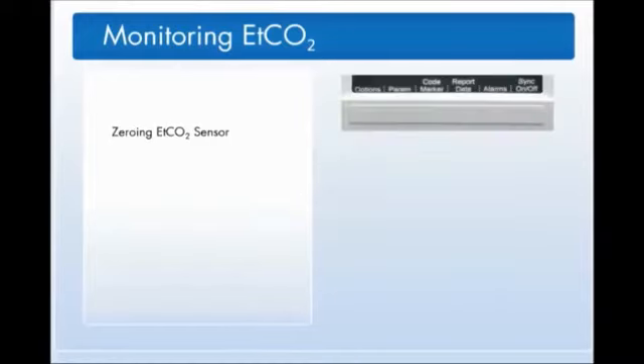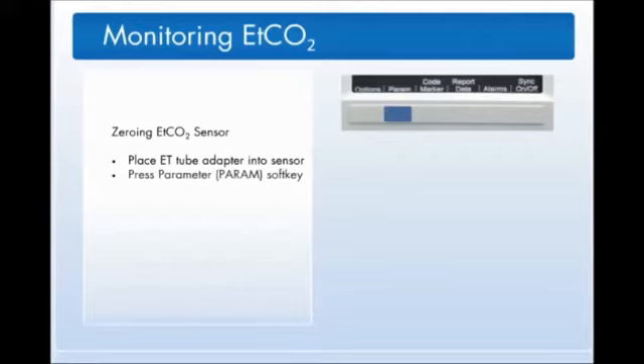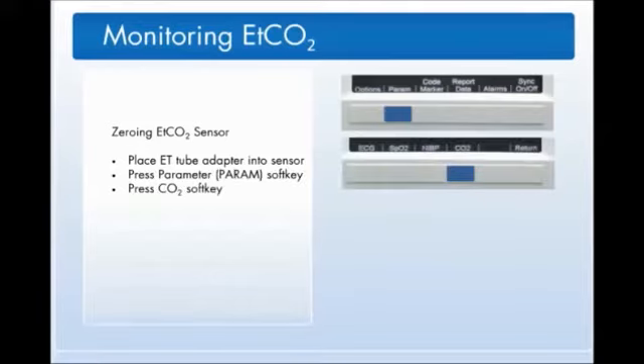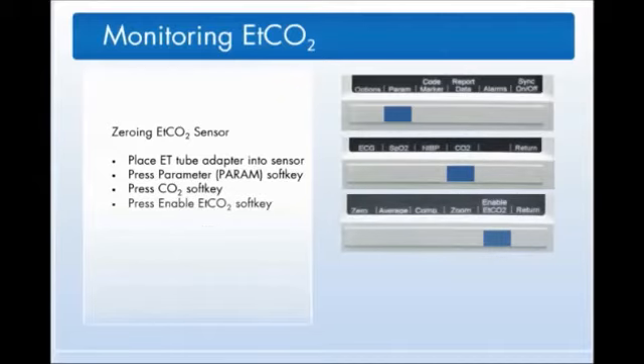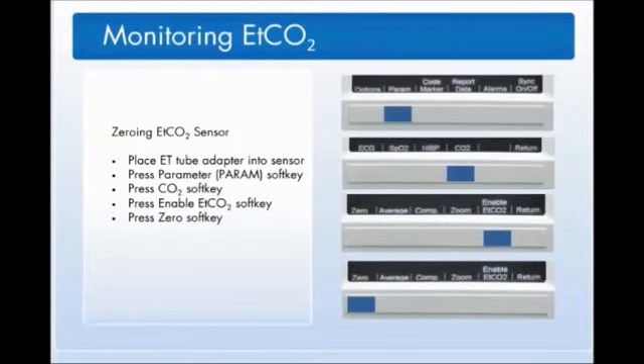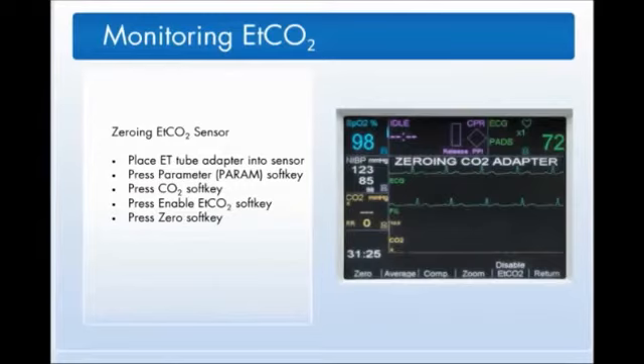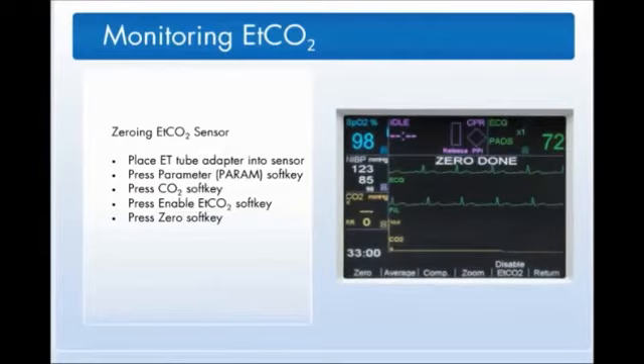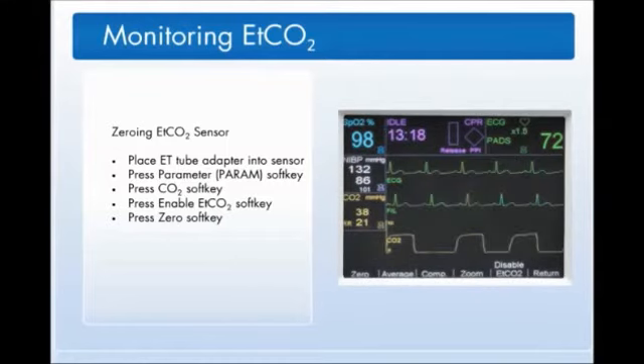The first time the EtCO2 sensor is plugged into the R series, the unit will need to be zeroed. Place the ET tube adapter into the sensor. Do not connect to the patient. Ensure that the sensor is away from carbon dioxide sources. Press the Param soft key. Then press the CO2 soft key. Then press the Enable EtCO2 soft key. Press the Zero soft key. The message Zeroing CO2 Adapter will flash. Once the zeroing process is complete, connect the adapter to the patient's ET tube or capnomask.